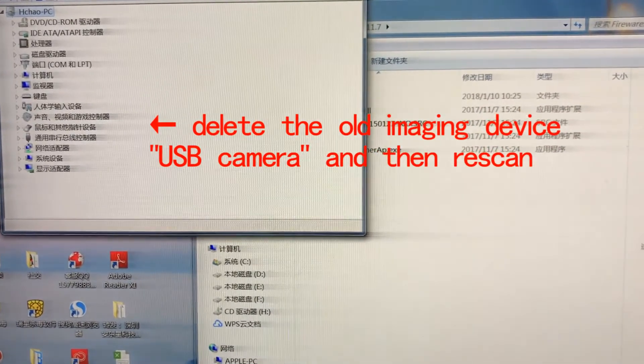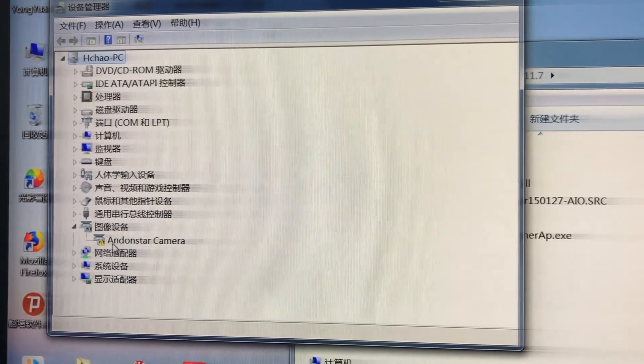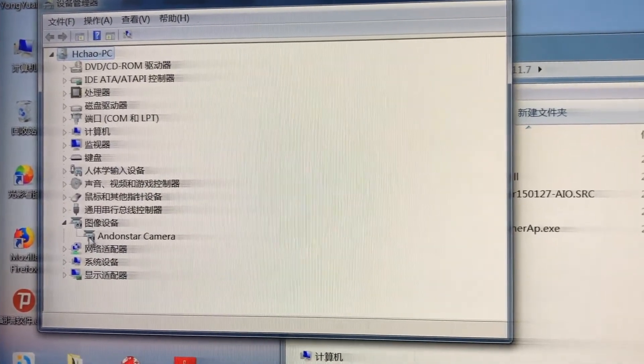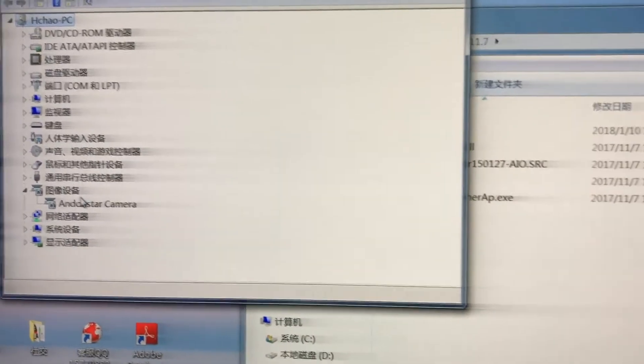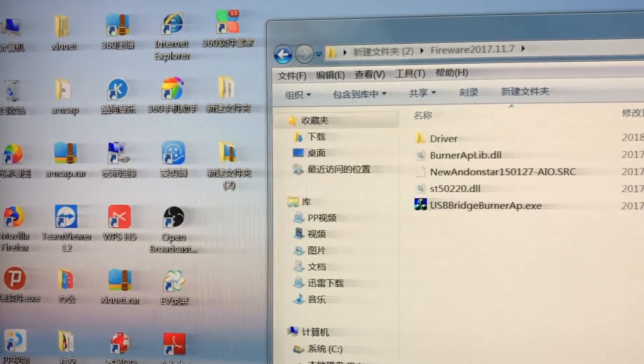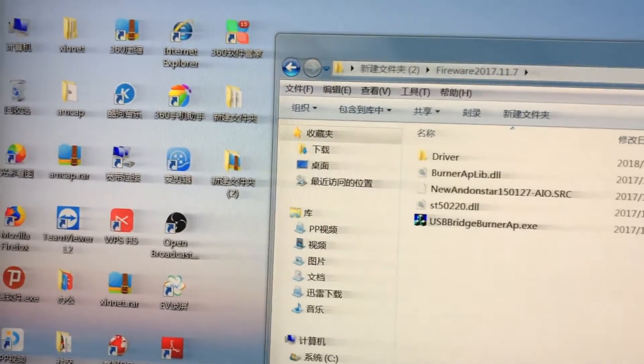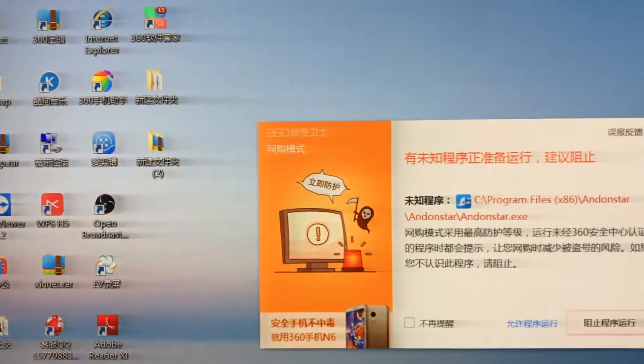Delete this USB camera, and rescan it. Wait until this yellow triangle is gone, and then it says Andonstar camera now, and then you open the software again.